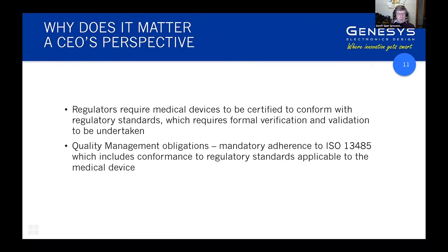From a CEO's perspective, the primary driver is, if you want your device to be legally saleable on the market, then you have to go through the verification and validation activities in order to satisfy ISO 13485 quality system requirements. The requirements of the various regulators, TGA, FDA, EU, etc., all align with the requirements of ISO 13485 and the other headline regulatory standards that lead into the certification process.